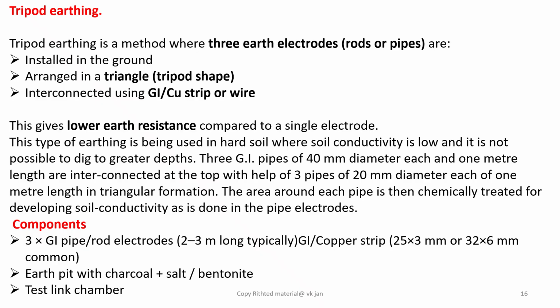Friends, we may require tripod type of earthing in areas not having very good soil, hilly areas. It is used to increase the effectiveness of earthing. Tripod earthing is a method where three earth electrodes are installed in the ground, arranged in a triangle formation, that is tripod shape. All the pipes are interconnected on the top using GI or copper strip or wire. Tripod earthing gives lower earth resistance compared to a single electrode. This type of earthing is used in hard soil where soil conductivity is low and it is not possible to dig to greater depth.